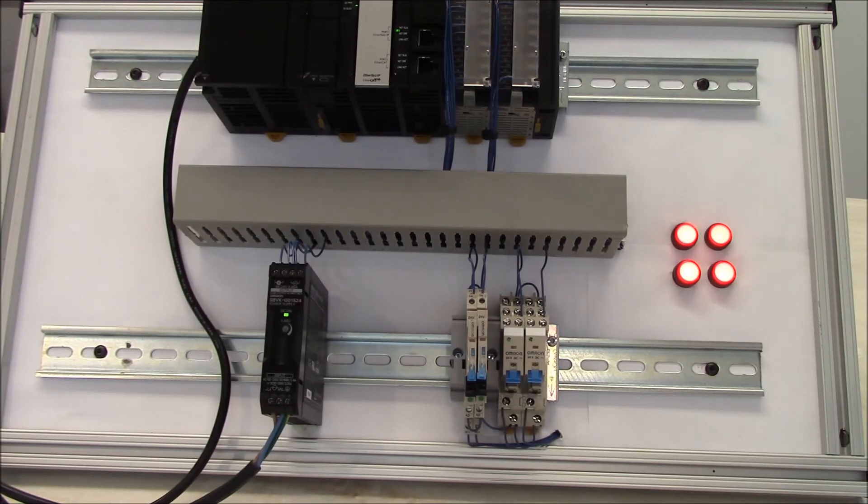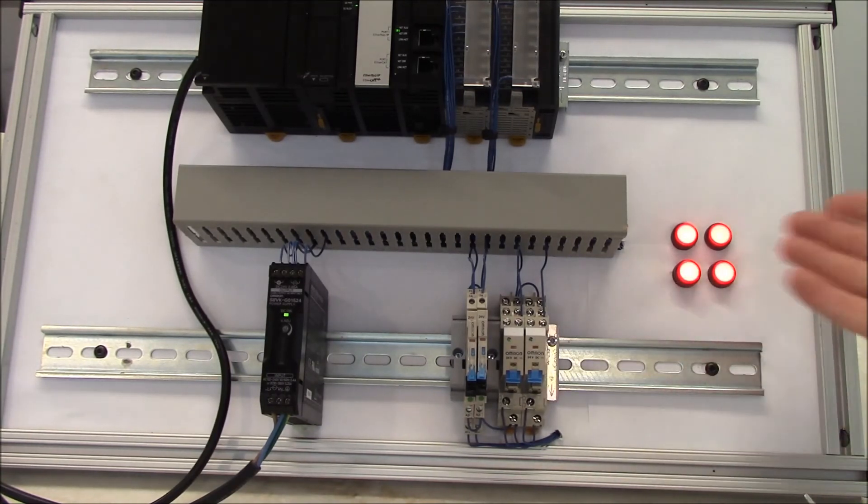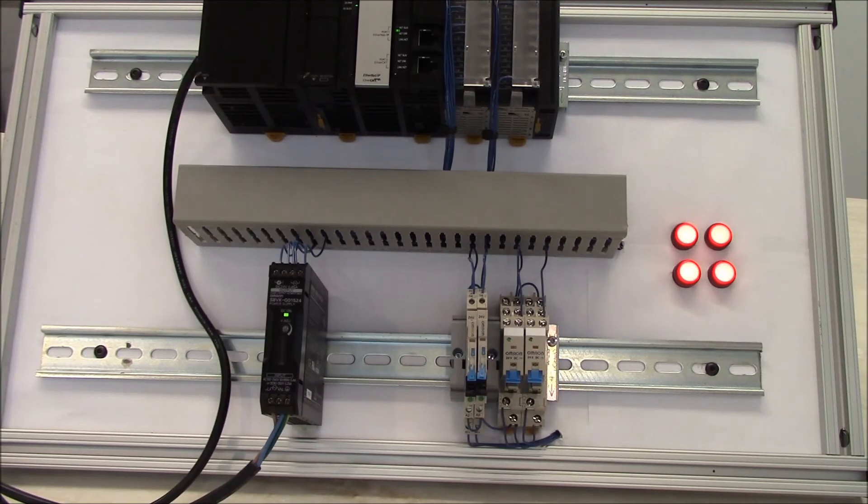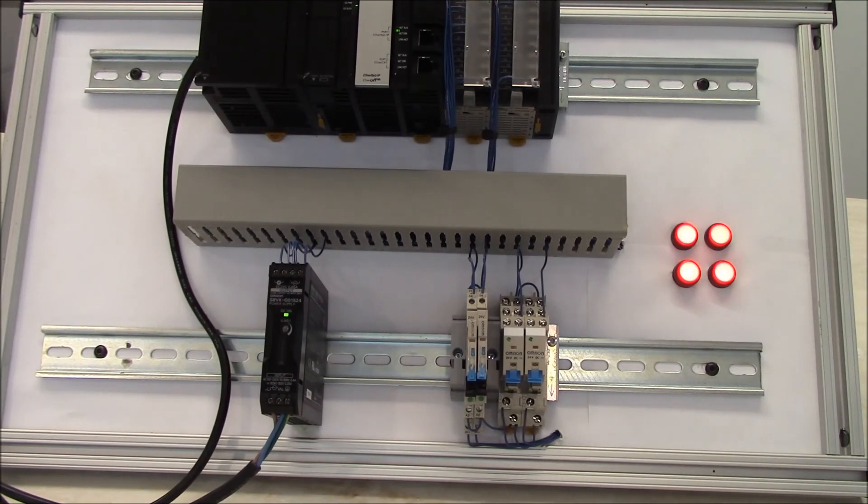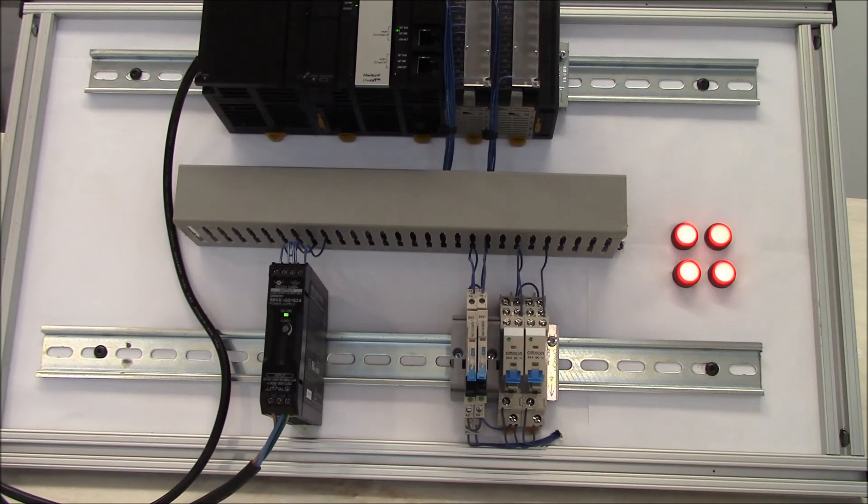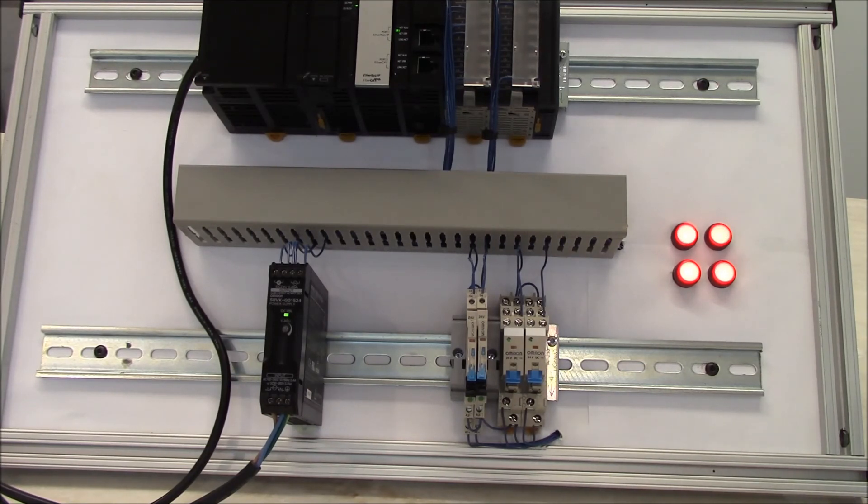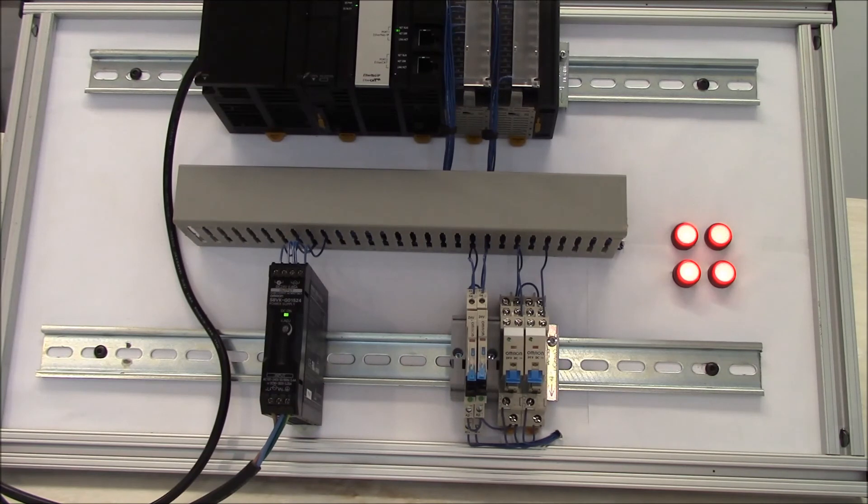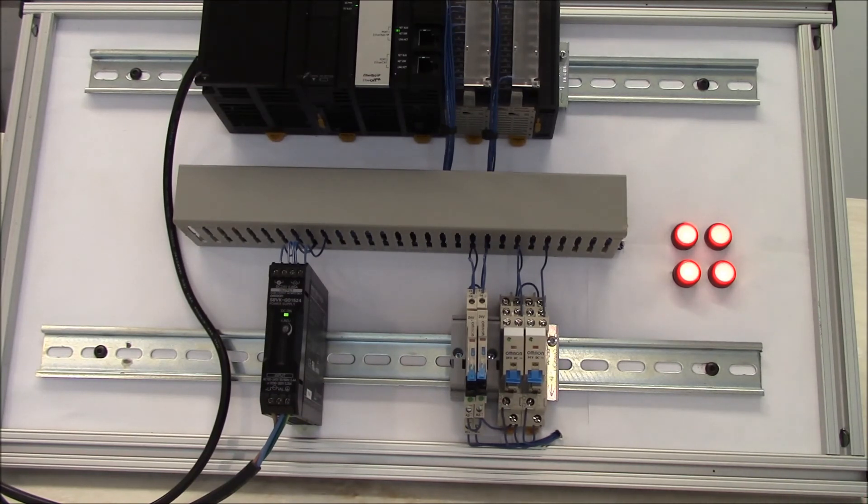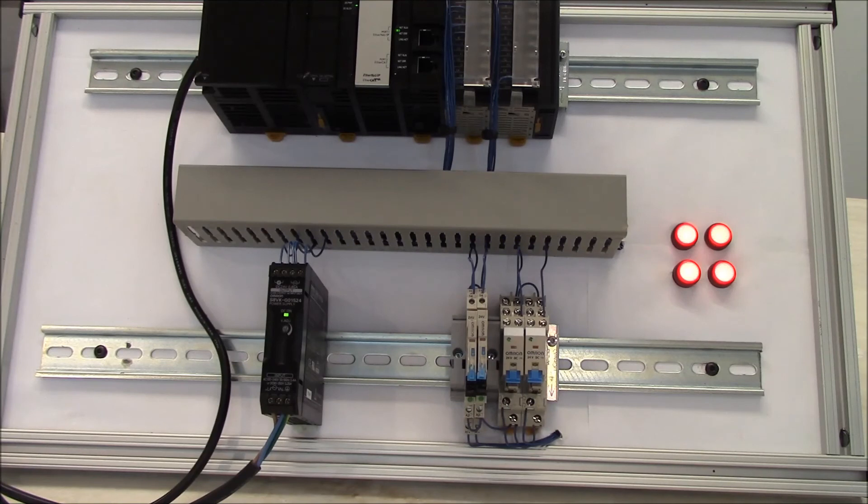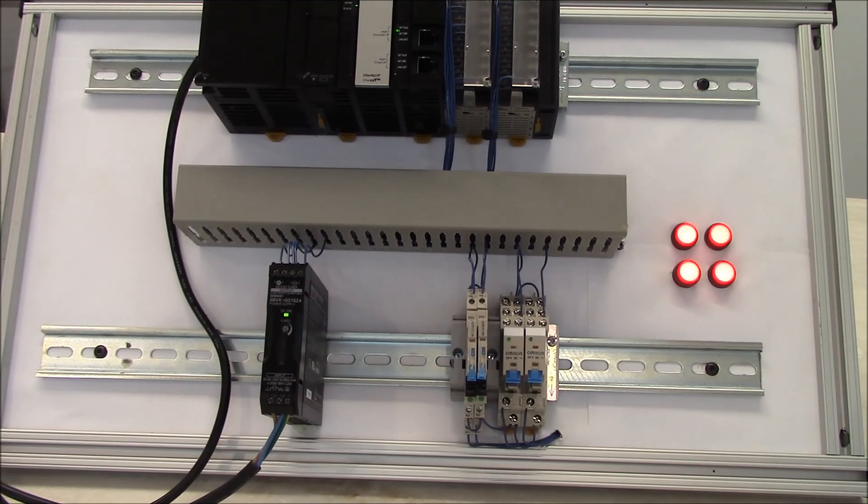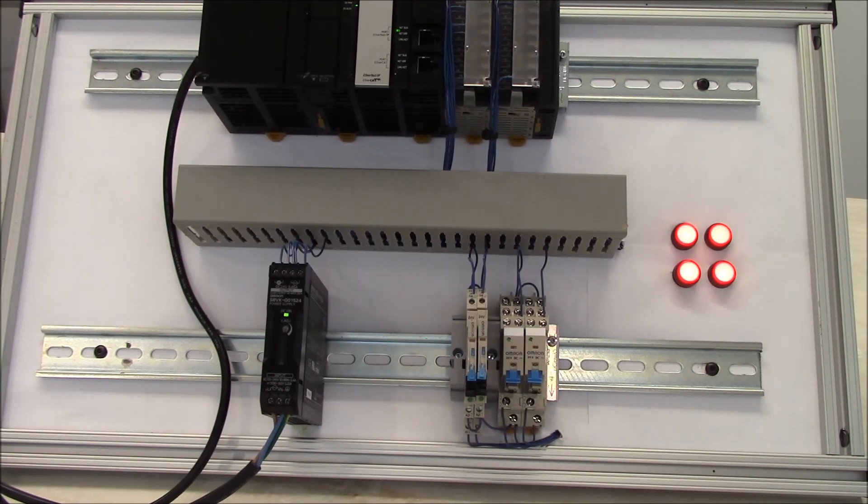I can test to make sure that my wiring from the relay output to the devices are set correctly. Let's say, for example, if I have the outputs wired to a pneumatic cylinder, I can sit there and I can actuate the cylinder, make sure my air flow valves are set proper before the programmer even gets down. Or if it's on a hydraulic application, I can make sure the pressures are all set right. So in either case, it does save a lot of time having the lockable test buttons available on the relay.